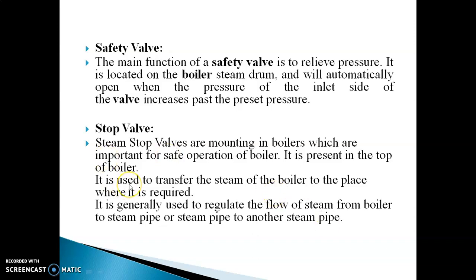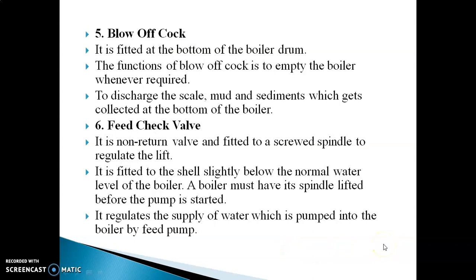Stop valve. Steam stop valves are mounted in the boiler, which are important for safe operation of the boiler. It is used to transfer the steam of the boiler to the place where it is required. It is generally used to regulate the flow of steam from boilers to steam pipe or steam pipe to another steam pipe. Blow-off cock. It is fitted at the bottom of the boiler drum. The function of blow-off cock is to empty the boiler when required.